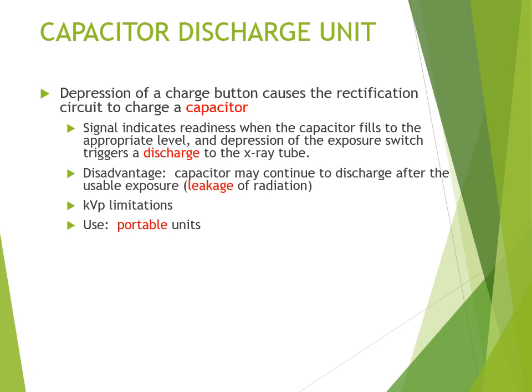The capacitor discharge unit: depression of a charge button causes a rectification circuit to charge a capacitor. The signal indicates readiness when the capacitor fills to the appropriate level. Depression of the exposure switch triggers a discharge to the X-ray tube. The disadvantage is the capacitor may continue to discharge after usable exposure, which gives leakage of radiation. And so kVp limitations were an issue too. So portable units are a possible application.